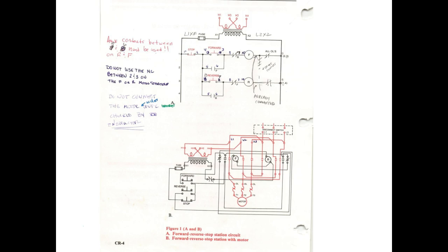Just remove L1, L2, and L3. So I want L1, L2, and L3 to be put on there last, right? You understand? And just leave it wired up for low voltage. So that means later on when you come back and do some of these motor labs, all you have to do is just bring the L1, L2, and L3 back down.